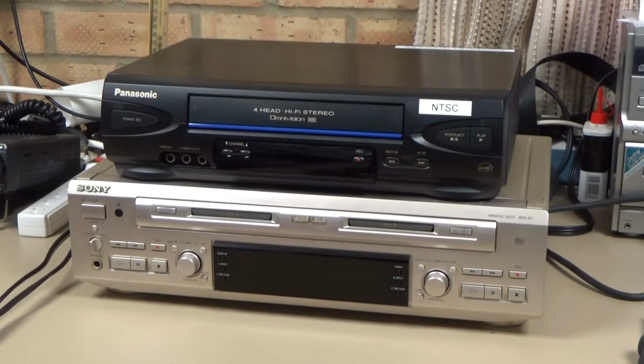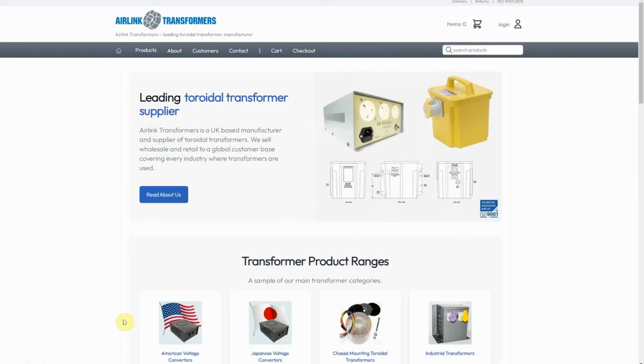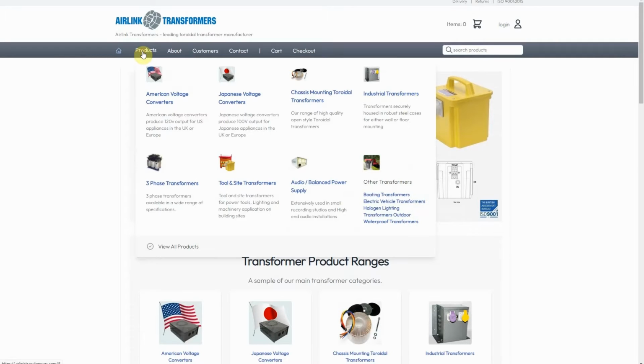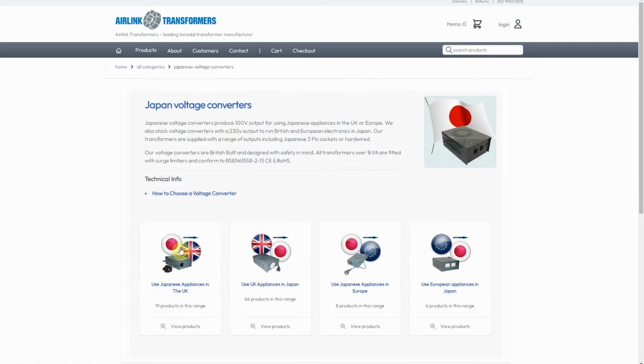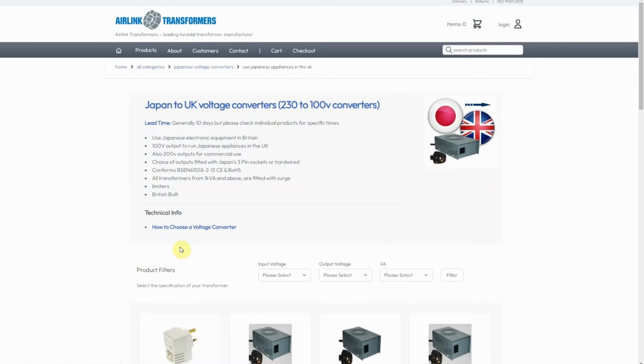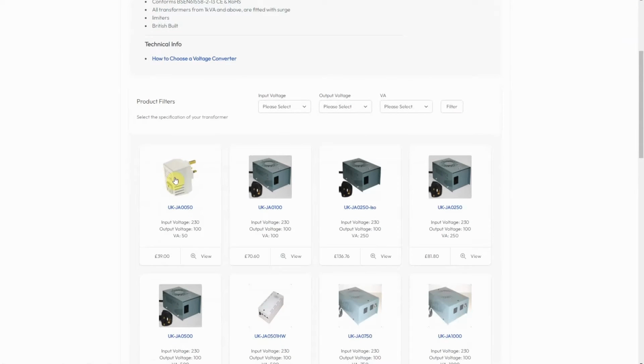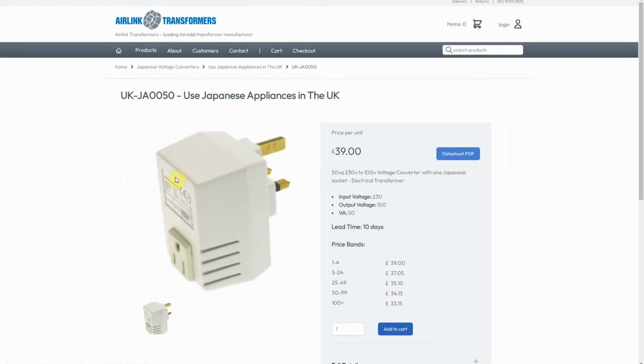Furthermore, it's surprisingly difficult to find step-down transformers that will convert 240 volts to 100 volts. I know Airlink Transformers is one manufacturer in the UK. In fact, even these transformers are designed for 230 volt input, so it outputs about 104, 105 volts when used in the UK. But that's likely to be within tolerance for Japanese equipment, and it's certainly a lot better than the 120 volts you'd get out of a typical US step-down transformer.